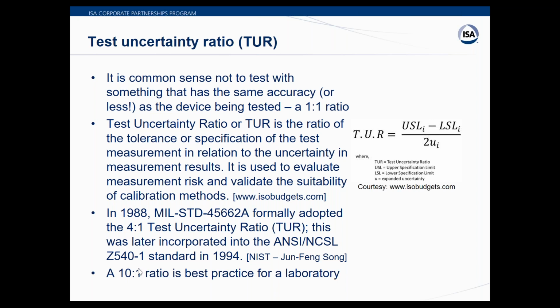And I'm going to throw this concept out. In our laboratory at BMEX, we try to have a 10-to-1 ratio, and we don't always achieve it on all our components. But for instance, when you're checking the multimeter part of our calibrator, we use a nice laboratory meter that maybe has 6 decimal places of resolution, and we're checking the 4 decimal places on a milliamp readout. So in that case, we probably have better than a 10-to-1 ratio. So again, this is a target. It's not an absolute, or you're not going to fail if you're not achieving these results, but it's a way for you to analyze and get to where you need to be to make good quality measurements. And just to reiterate, today's instrumentation is better than ever.